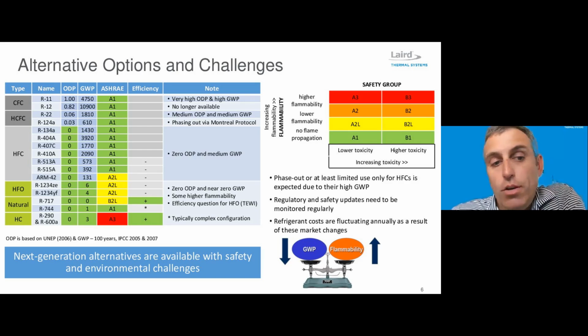As we get into where we are today with alternative and natural refrigerants, you can see that there's still a zero ODP, a greatly reduced GWP, and an increased flammability and toxicity of the refrigerants as we go to some of these propanes and isobutanes that are being used for cooling.